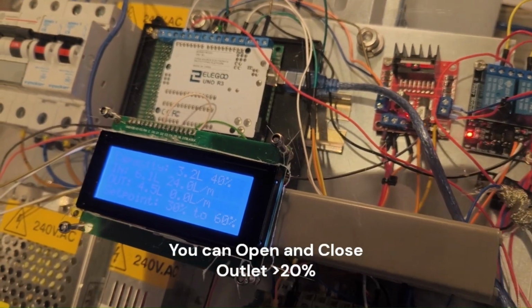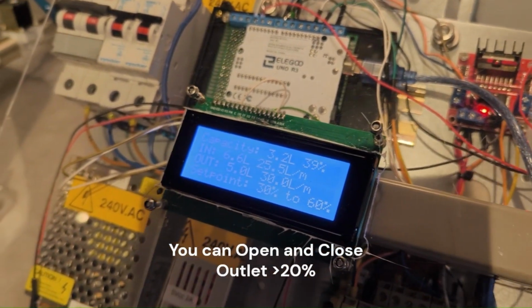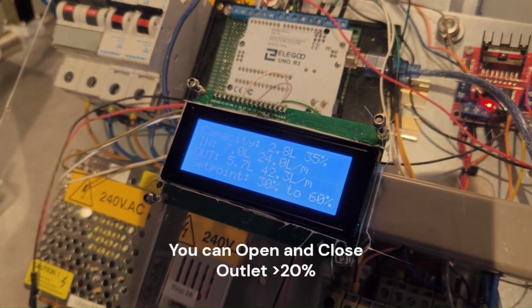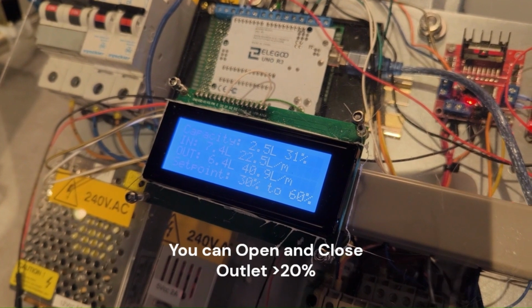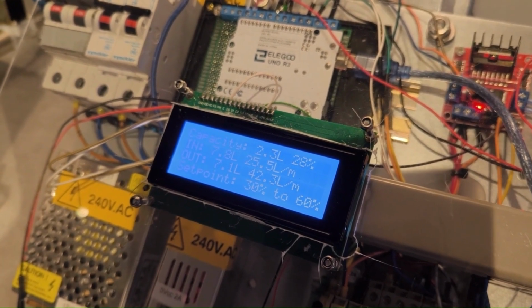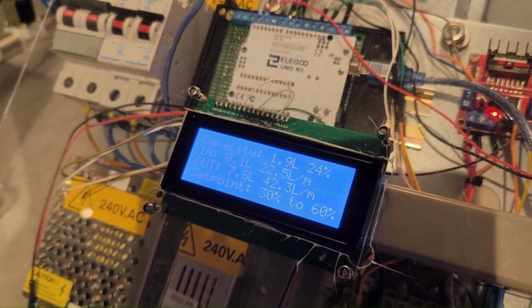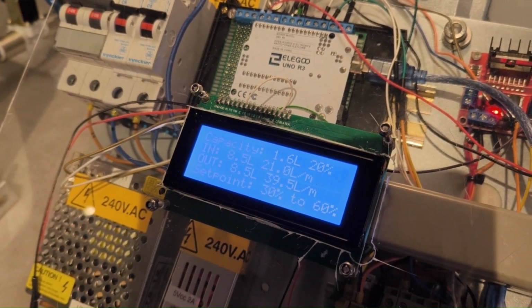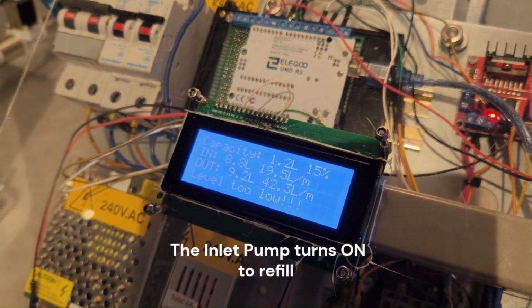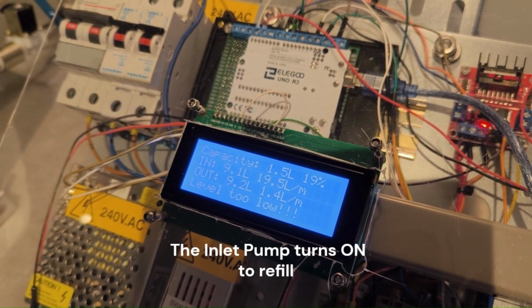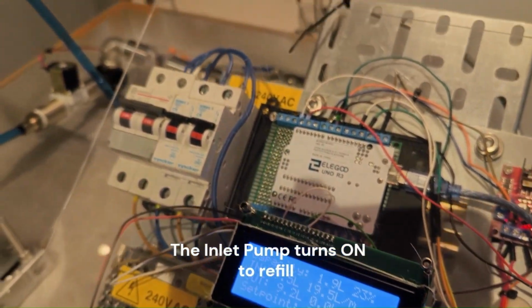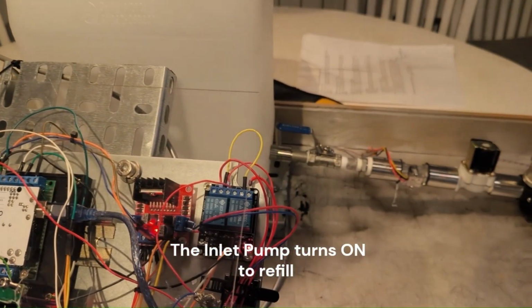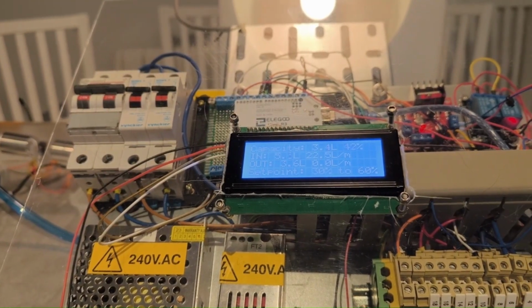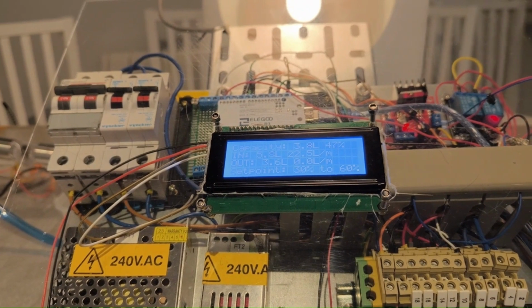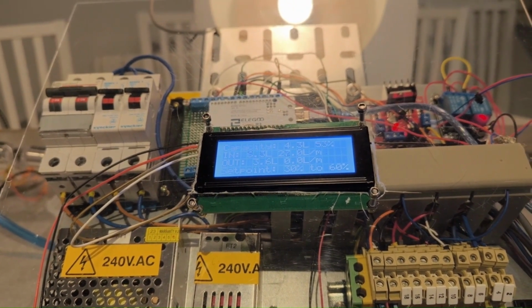If it's more than 20%, you can open and close the XV101, the outlet valve. If it's less than 20, it will stop automatically. We'll raise until it gets to the maximum set point, which is 60%.